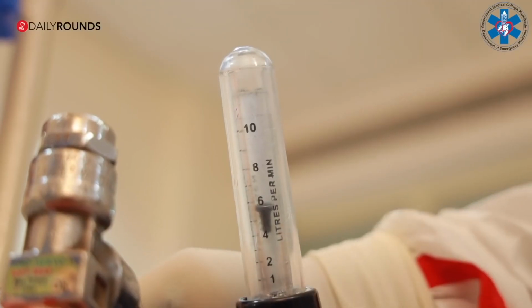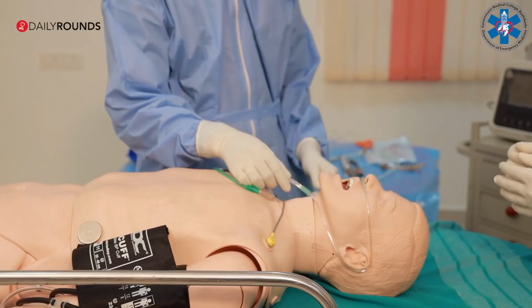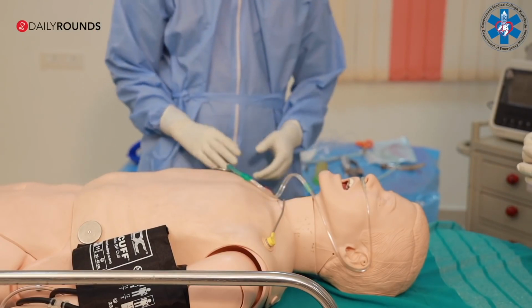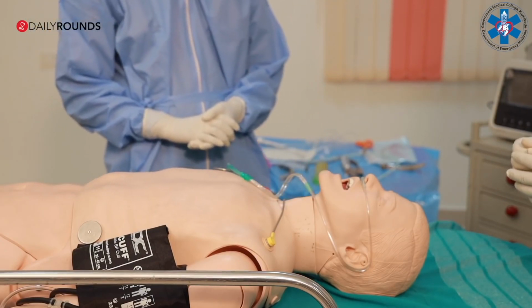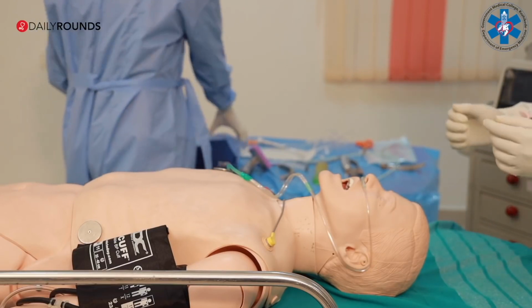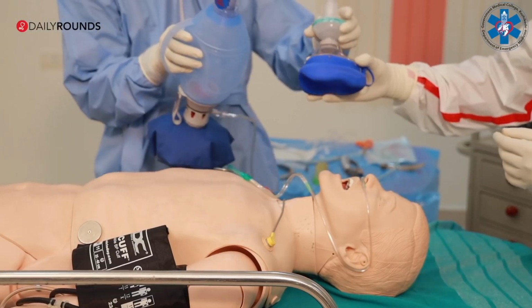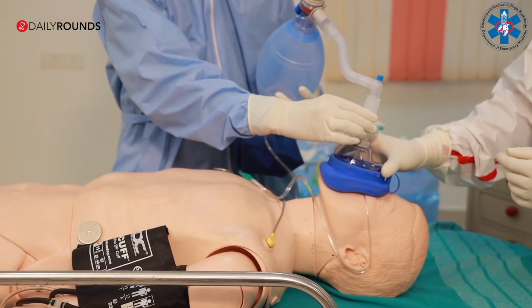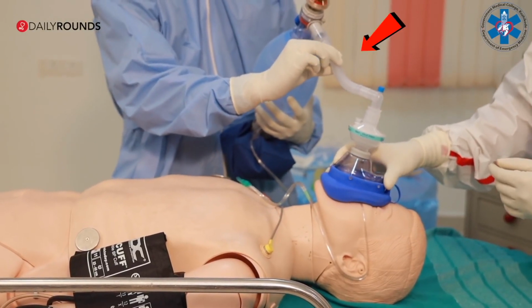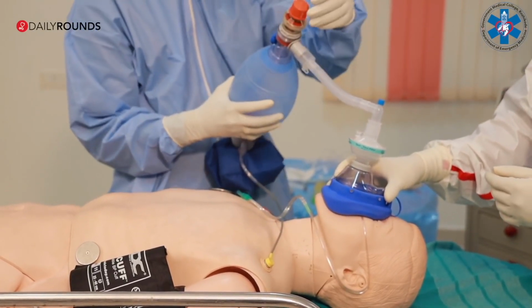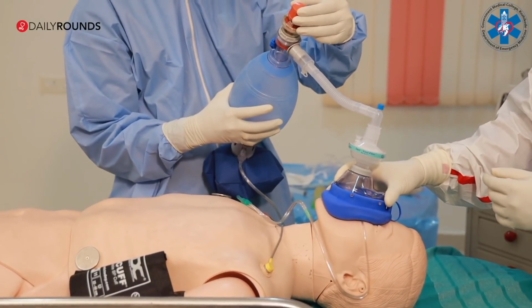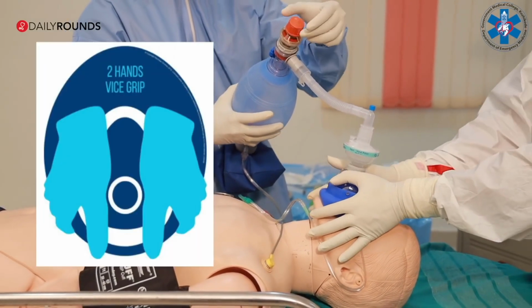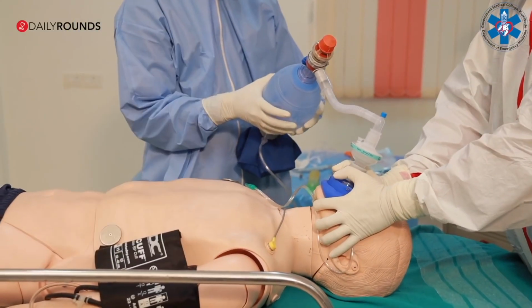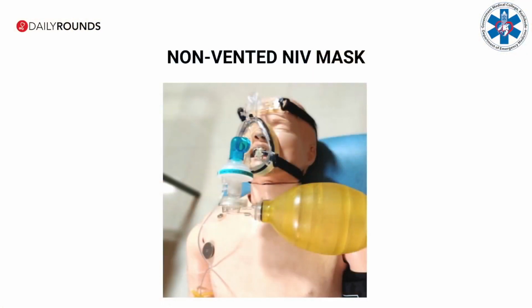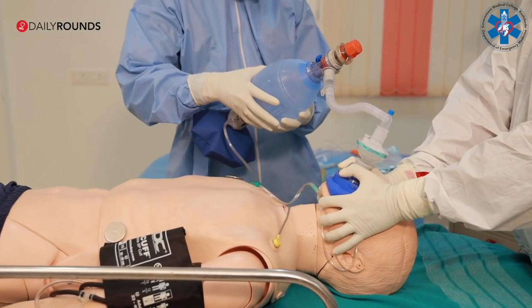And set a flow of 6 liters per minute. This can provide apneic oxygenation as well as apneic CPAP. Use a bag mask ventilation device with a viral filter and a flexible catheter mount to provide leverage, and a PEEP valve if available between the mask and the bag. Use a firm two-handed vice grip to prevent any leak. A non-vented NIV mask of optimum size may be used to achieve a better seal.